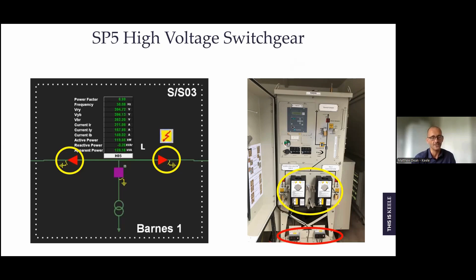SP5's also got something called a study mode. So basically this is kind of like a digital twin. So we can use this to simulate the effect that performing switching operations will actually have on the network. So if we've got any planned maintenance, or if we're adding another substation, for example, and we're going to have to start switching, we can actually put the system in study mode, perform those switching operations, and we can see exactly which parts of the network are going to be de-energized and make sure that there's no unintended consequences.